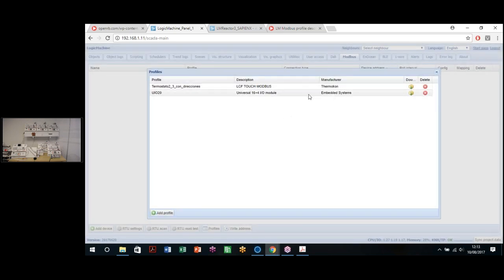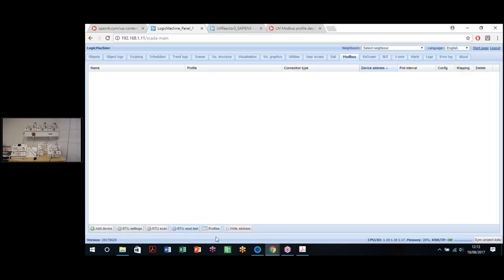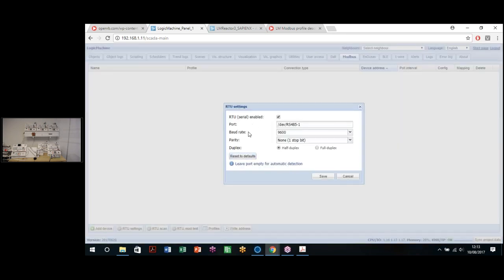It has the address already set. We, of course, can download this profile so we can edit it if we have made any mistakes, or we can also download it for use as an example for creating new profiles. So once we have uploaded this profile, we're going to configure the RTU settings of the Modbus port of the RS-485 bus. In this case, we're using RTU communication. LogicMachine also supports Modbus TCP communication. It's configured differently. We are going to see that either way.